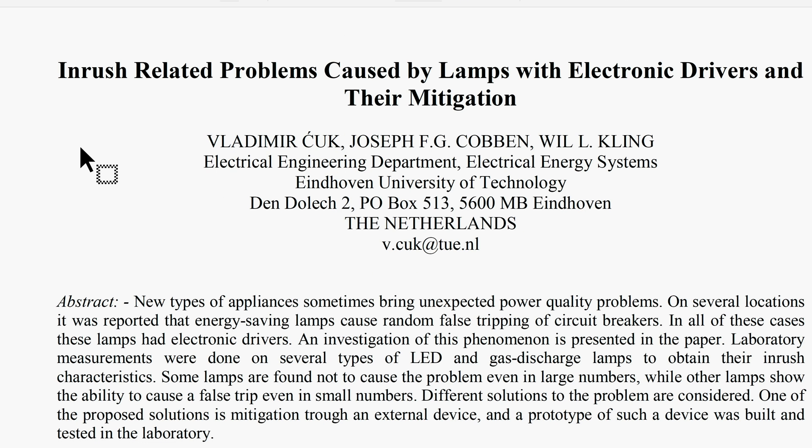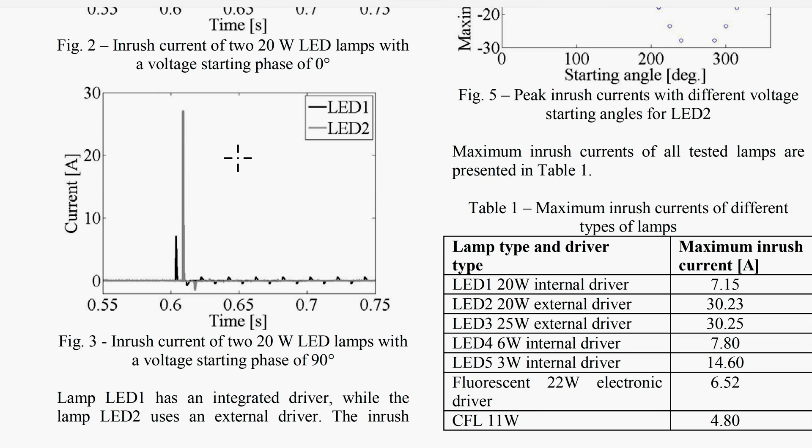Then I have located this article which says inrush related problems caused by lamps with electronic drivers and their mitigation. Right. I'm just going to show you two things that the authors have demonstrated. Here are some of their waveforms. And one can see that they were just testing a 20 watt LED lamp. And you can see that they also had these very high peaks. Considering that this is the 20 amp mark, so this is above 25 amps. And considering that this is only a 20 watt LED.